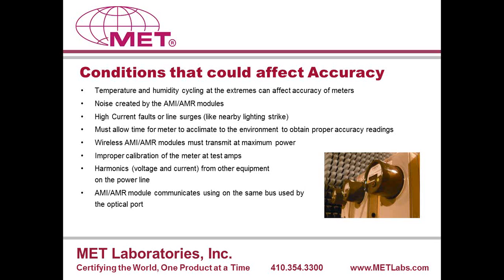Allowing the meter to acclimate to the environment. So essentially you don't want to power the meter on and start taking accuracy measurements right away. Typically there's some warm-up period that you need to consider before you get into the accuracy testing.